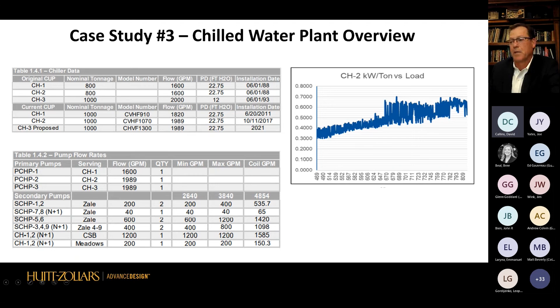But when we start looking at this, this is the energy of one of the chillers, the kW per ton, over the points of the capacity over a few thousand hour points. You can see they're spiking here and there. The reason being, we showed that they never increased the tower, the condenser, the cooling towers. And that affects the efficiency greatly. So we're like, okay, that's a problem.